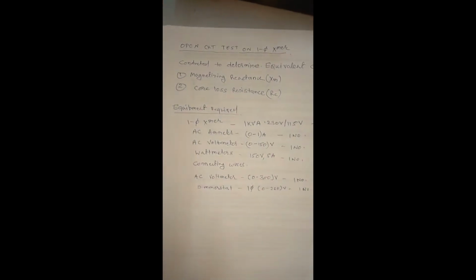Today we are going to perform the open circuit test on a single phase transformer in our electrical machine labs. This test is conducted to determine equivalent circuit parameters. These parameters include magnetizing reactance XM and core loss resistance RC. This test is performed on the LV side of the single phase transformer and the HV is kept open.